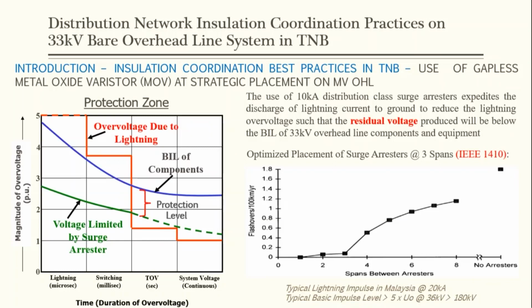And from this graph, for optimized placement of surge arrestor as per IEEE 1410, if we put one surge arrestor every 3 spans, we can minimize the effect of lightning overvoltage. But if we don't put any arrestor, the flashover per 100 km per year will definitely increase. So between 1 to 3 is acceptable in terms of flashover per 100 km per year.